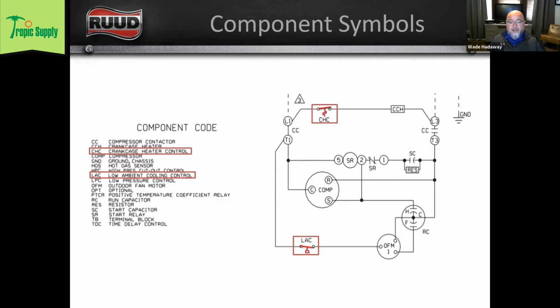That tells me that this low ambient control opens on a drop in pressure, because we can't push it up any higher, right? If we were to invert that and have that red line on the top of the switch contact, it would open on a rise in pressure. But just looking at it, I see that I've got a low pressure control and a high temp control, and that's what these two symbols are telling me.